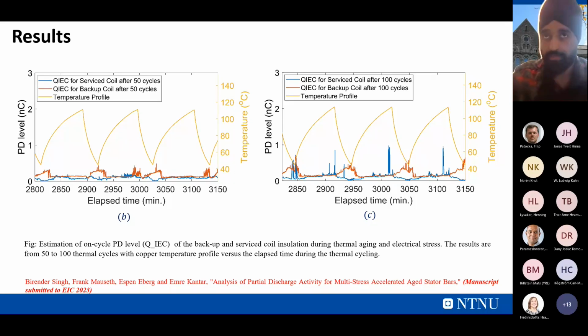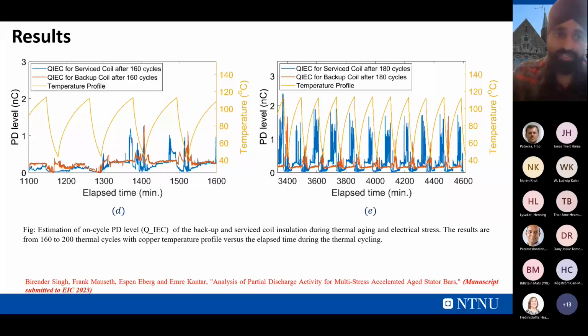But at around 160 cycles, we observe that the service coil, which is already in service, starts showing increasing PD values, and it shows a uniform pattern in which it keeps on increasing like this. These blue lines for the service coil continuously increase till 200 cycles. After 200 cycles, we again tested the tan delta values and found that they are also much higher, which gives an indication that something is happening, or maybe the number of defects inside the insulation has increased.